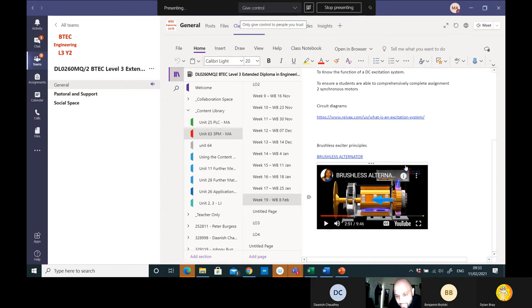What you've got here is this. As the rotor spins, you've got a device here, and that gets energized with AC electricity as it spins through the magnetism across here to here. It produces an electric field, so you've got some kind of induction happening. And there's a diode here. These diodes, it's called the diode wheel. That diode wheel takes that AC, converts it into DC automatically, and sends that DC to the rotor magnet instead. So it's a very clever way.